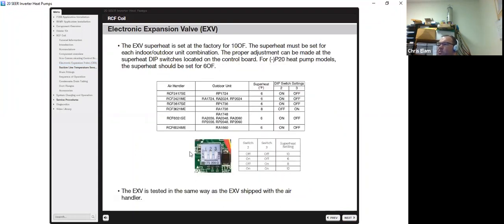This kind of goes over your dip switches again. Your switch 1 is for your motor. You put that on, the motor will now think it's a 1600 step instead of a 500 step, and you end up with some erratic operation. 2 and 3, so off and off, in this case, gives you a pre-configured superheat setting of 10. If you want to change it to 6, 8, or 12, you can by adjusting 2 or 3.